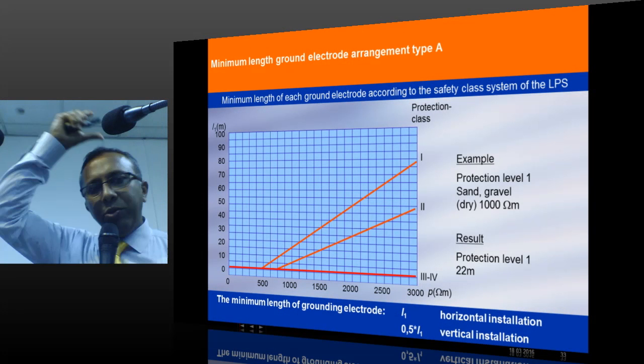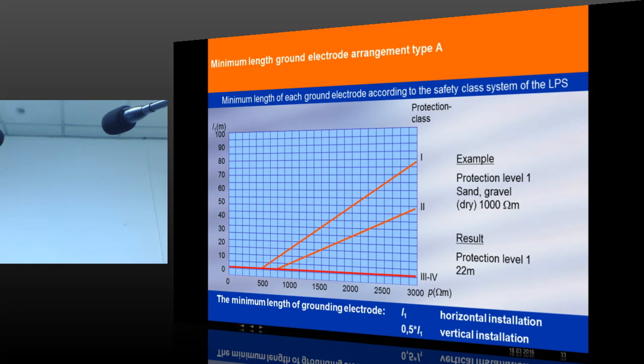If you are using type A, the next argument is what is the electrode resistance, the earth resistance. The maximum value recommended in the standard for earth resistance is 10 ohms. It is also not a condition. One of the conditions is you have to have 10 ohm earth resistance, and the second condition is the 10 ohms can be skipped under this condition.